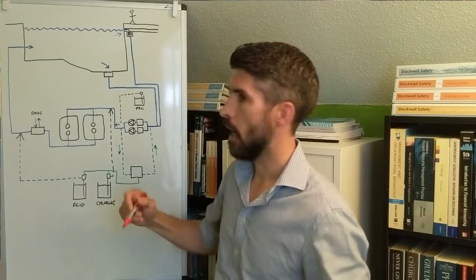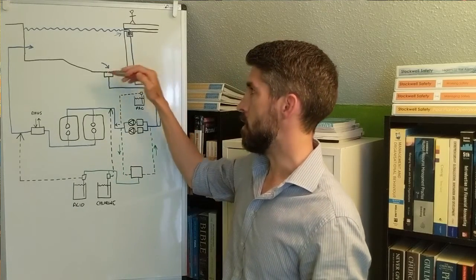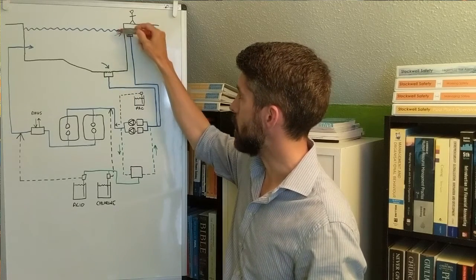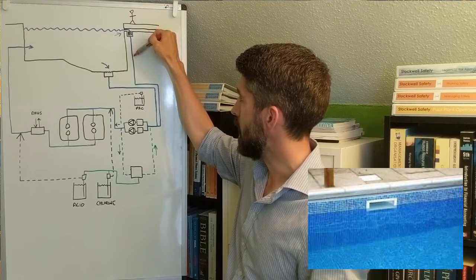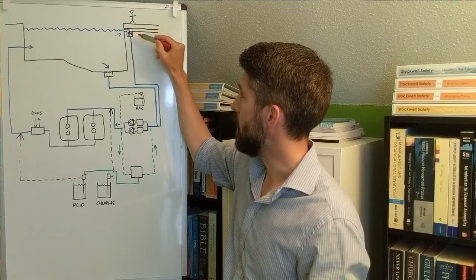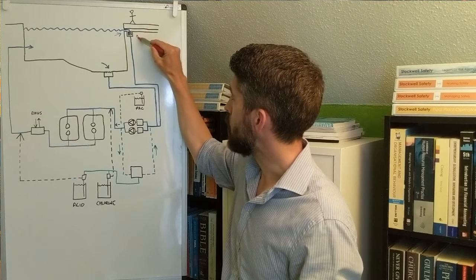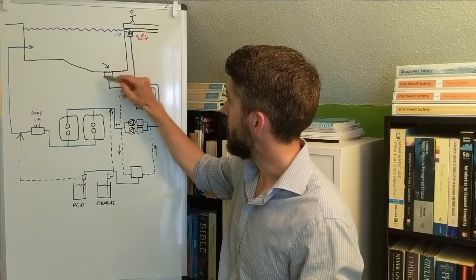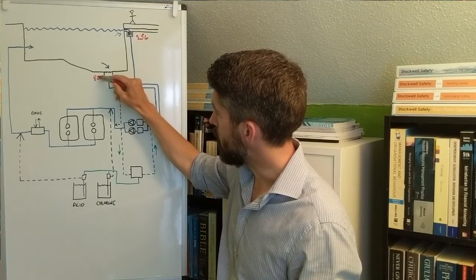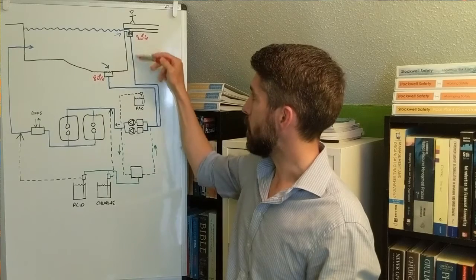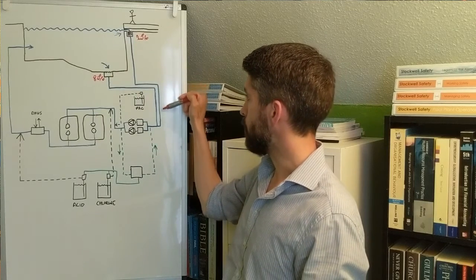You've got water exiting the pool in two main areas: the surface water draw-off system, so water comes through the skimmer baskets here, and also via the sumps or drains. A typical distribution between these two outlets is usually 20% of water going by the skimmers and 80% of the water flow at the sump.